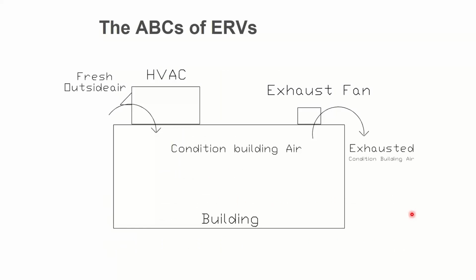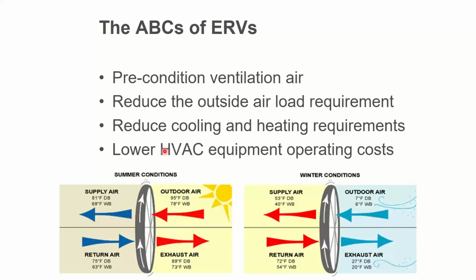One of the keys is in getting the exhaust air near the intake air. If my intake's over here and my exhaust is on the other side of the building, that's going to be tough to do. Because I need to get his BTUs out of this guy and transfer them over to this guy. So I need the intake and the exhaust to be close to each other, preferably through the same piece of HVAC equipment if I can get it to happen. What's this all going to look like?